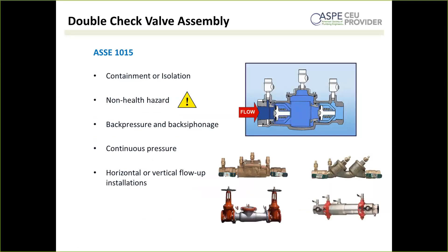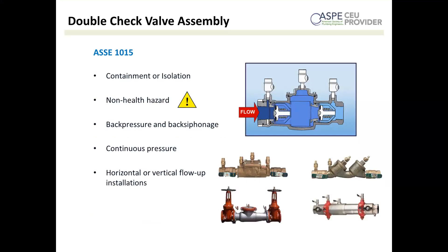Double check valve assemblies, ASSE 1015, are typically available from half-inch all the way up to 10-inch sizes. These are for containment or isolation — point of source or point of use — for non-health hazard applications, and they handle back pressure, back siphonage, and continuous pressure. They can typically be installed horizontally or vertically with flow going up. Like dual checks, these are essentially two single checks. The main difference is that they must be testable — you'll notice four test cocks on every example: one upstream, one downstream of the first check, one in the zone between the two checks, and one after the second check.